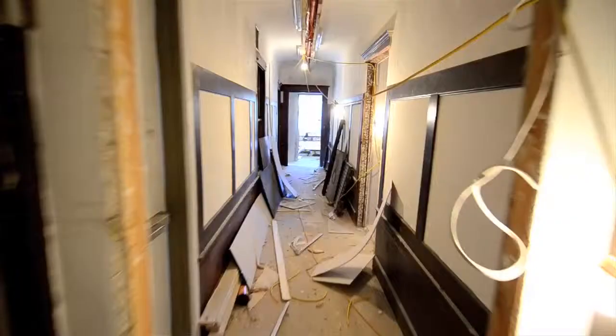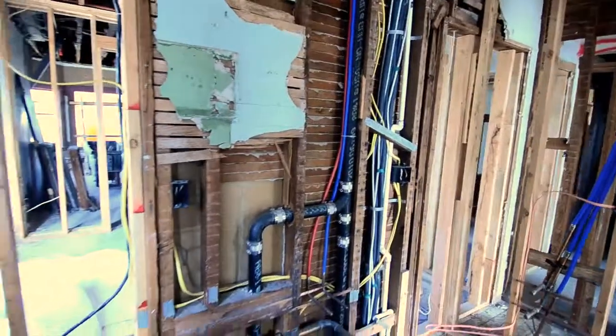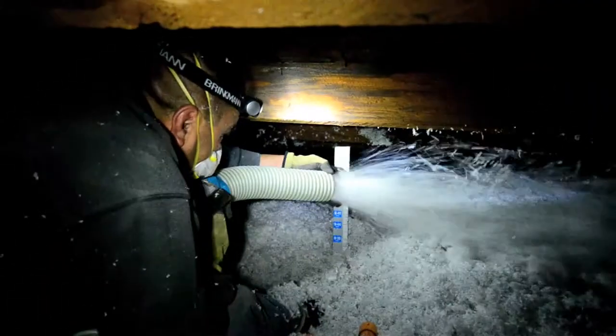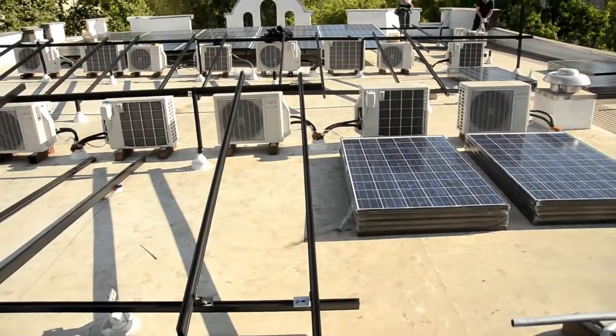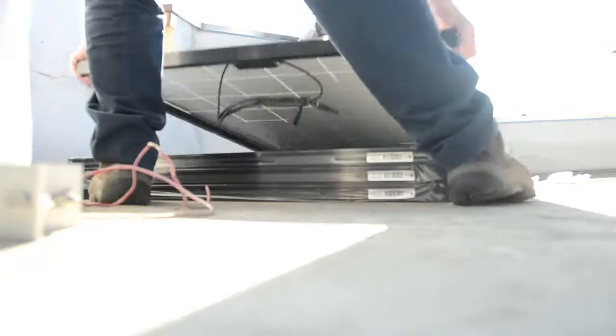This building is 100 years old. It needed a major renovation of all the systems — the mechanical system, the lighting system, and the building envelope. There was no insulation in the building whatsoever, certainly nothing in the walls. We filled the attic cavity with blown-in fiberglass insulation to R49, so they really filled it all up. On top of that we put a cool roof, which is really great because it reflects heat off the roof and keeps the whole building cooler.